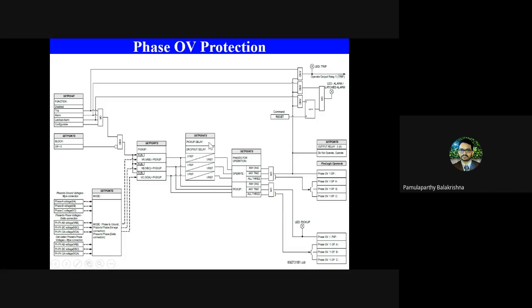If you configure a delay, as I explained, once the level has been crossed, it will start the timer and wait until the timer expires and the signal is sustained for that particular duration. Once it is sustained, it will check whether I need to operate on only one phase voltage, or two phases, or three phases. If all three phases are crossing this level, based on the values I see and the configuration, then I will operate the breaker. So PKP means the element has just picked up and didn't take any action as defined here. But once it sustains through the timer, it will operate, and the message "phase over voltage one has operated" will come to the operator.